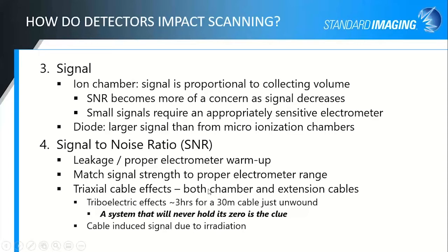Third way that your detector is going to affect your scans is signal. So with an ionization chamber, your signal is proportional to your collecting volume. So as you go down into these very small microchambers for scanning, you need to be sure that your signal to noise ratio is sufficient to give you a reasonable reading. Sometimes if you've got a high electronic noise floor or background signal, you may actually measure a little bit too high in the low dose regions because you're basically bumping up against that noise floor. It's a little easier to troubleshoot or to understand your electrometer behavior and the ranges often with our calibratable electrometers than necessarily the ones that are attached to a water tank.